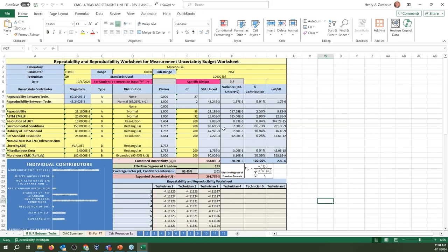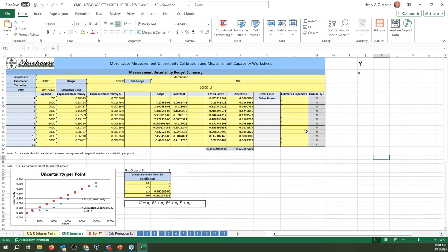Here's one. Repeatability, reproducibility filled out, CMC summary, everything's filled out. You can see expanded uncertainty. This is a UCM, a 10,000 pound load cell in the UCM. And at 10,000 pounds, you can see 0.0657%. You can also see at the 10% point, 0.0379. This is one that has automation with it.